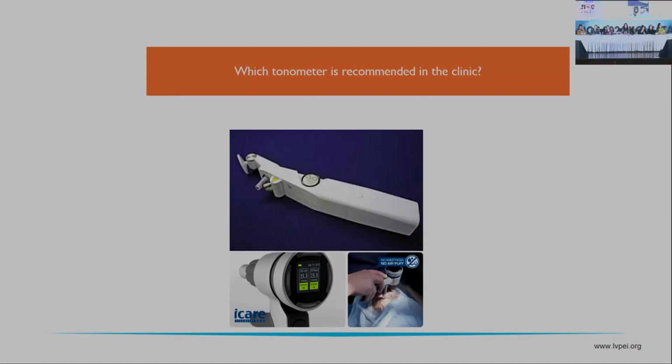Yes, that's what we do also. In a day, we don't reuse the probes on a different day. So this morning, if you open 5, 10, whatever number of probes, after we use the Icare probe, once we finish testing, before putting it into that small little plastic box, immediately hit it on the alcohol swab and let it dry, and then you can dislodge it into that box and leave it there.